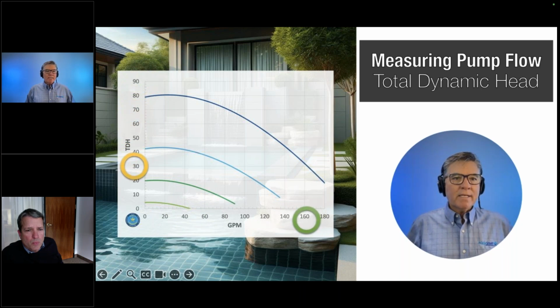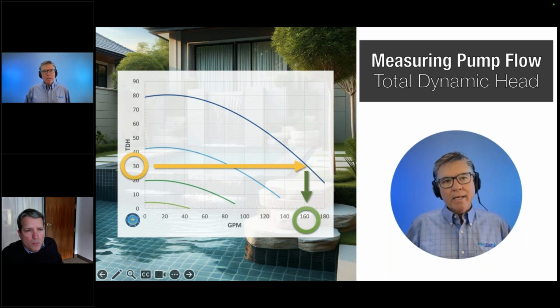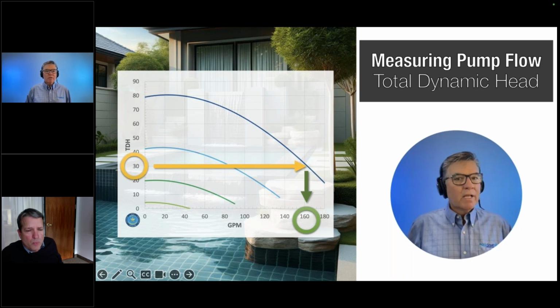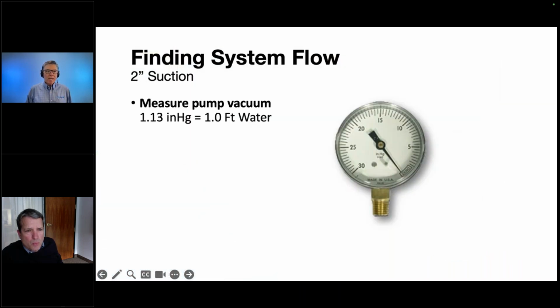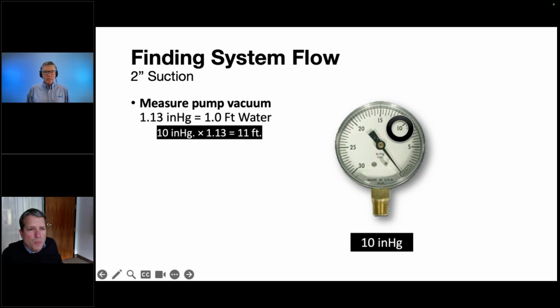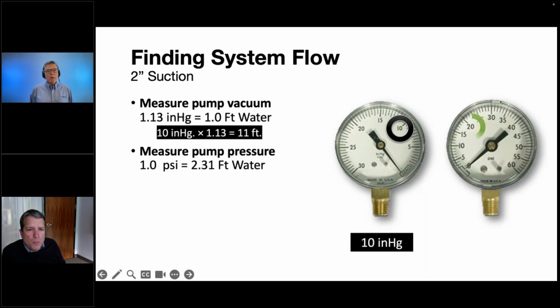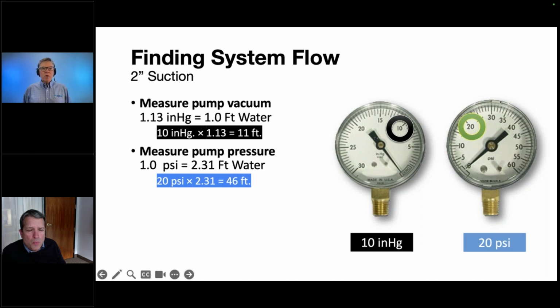So high TDH, low flow. If you have low TDH, you have high flow. And this is a 3 horsepower pump curve. Every pool, every water feature is a snowflake. So how do we find out what this actual pump is performing without a flow meter installed? This is the process. You measure the pump vacuum. There's your conversion factor, 1.13 inches of mercury gives you 1 foot of water. Measure the pump pressure. 1 psi equals 2.31 feet of water.